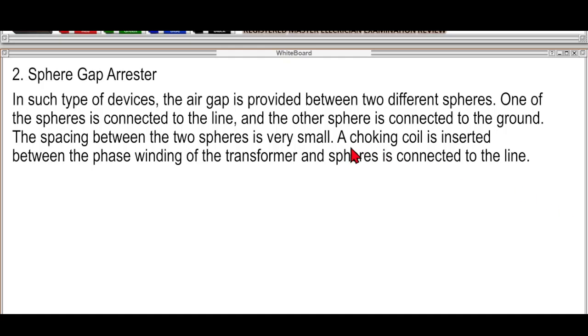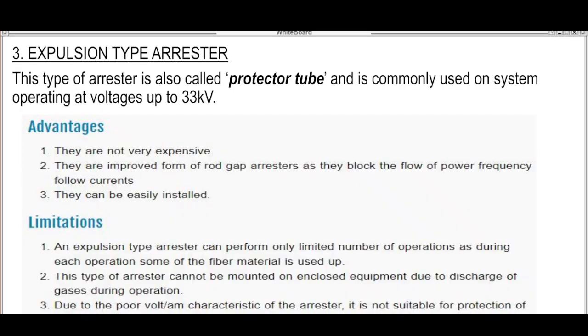Next, we have the sphere gap. In such a device, the air gap is provided between two spheres. One of the spheres is connected to the line and the other is connected to the ground. We have a choking coil inserted between the phase of the transformer and the sphere which is connected to the line. Then we have the expulsion type arrester.